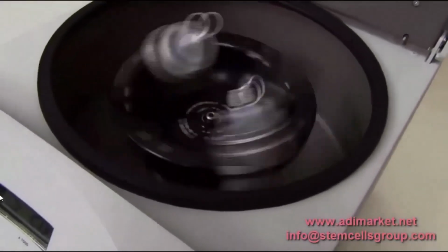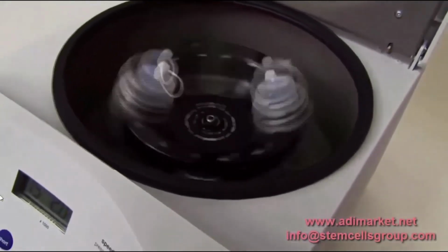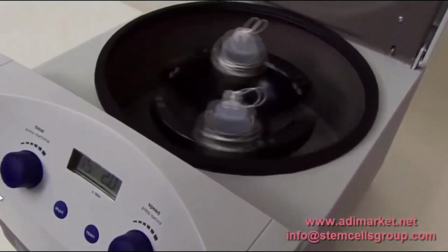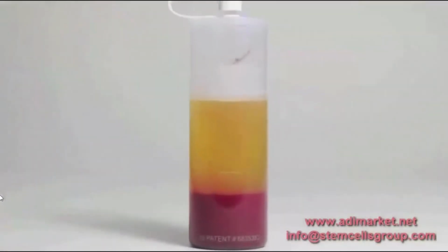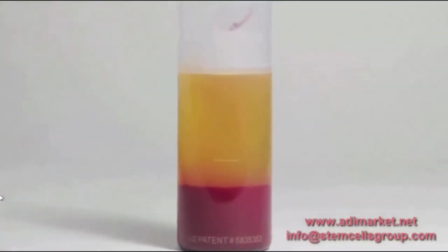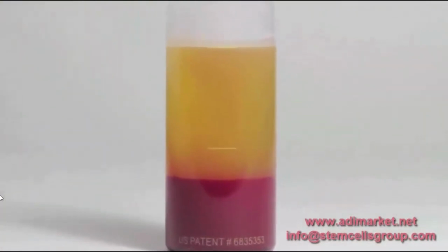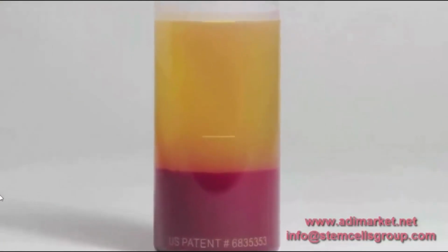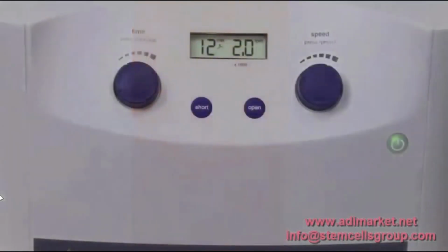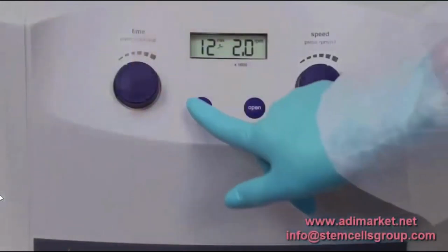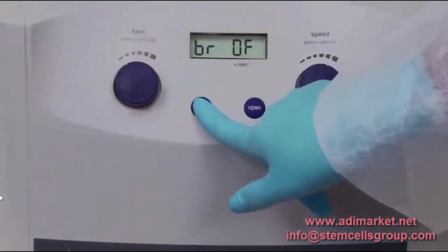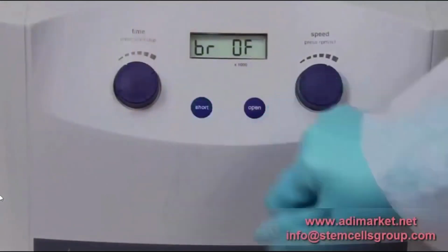The centrifuge comes with a controlled acceleration and soft braking feature. This minimizes cell agitation and resuspension during processing. Optimized separation is achieved without disruption, providing the best achievable cell concentration for your procedure. To activate this feature, press and hold the short button until you see BR off indicated on the display.